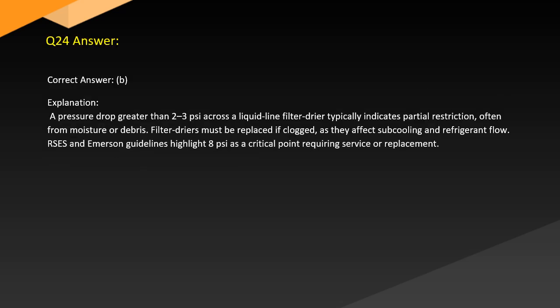Answer. Correct answer, B. Explanation. A pressure drop greater than 2 to 3 psi across a liquid line filter dryer typically indicates partial restriction, often from moisture or debris. Filter dryers must be replaced if clogged, as they affect subcooling and refrigerant flow. RSES and Emerson guidelines highlight 8 psi as a critical point requiring service or replacement.